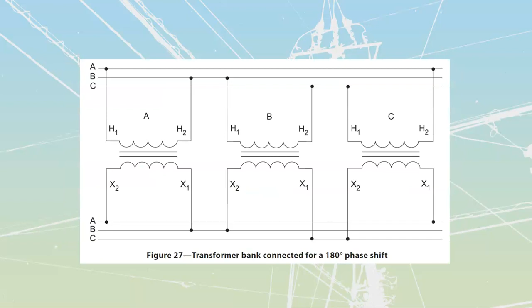And if it's double line voltage, that's going to be dangerous. The other thing we could do that's bad but not horrible is connect our transformer bank accidentally for a 180-degree phase shift, same as what we had inside our Y to Y connection. If we look at it, the high voltage side is correct.